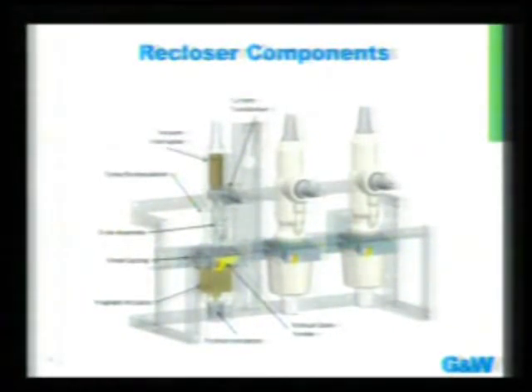As we look at whether power is available and how much is flowing through the recloser, we have current transformers that tell us the amount of power flowing through. If there's too much power flowing through, it's typically due to a problem on the system, and we will then open up. Some newer innovations in reclosers: we now have voltage sensors integrated not only on one side as in the past, but now on both sides of the recloser, which tells you, if it happens to be open, whether there's voltage or presence of power on one side versus the other.